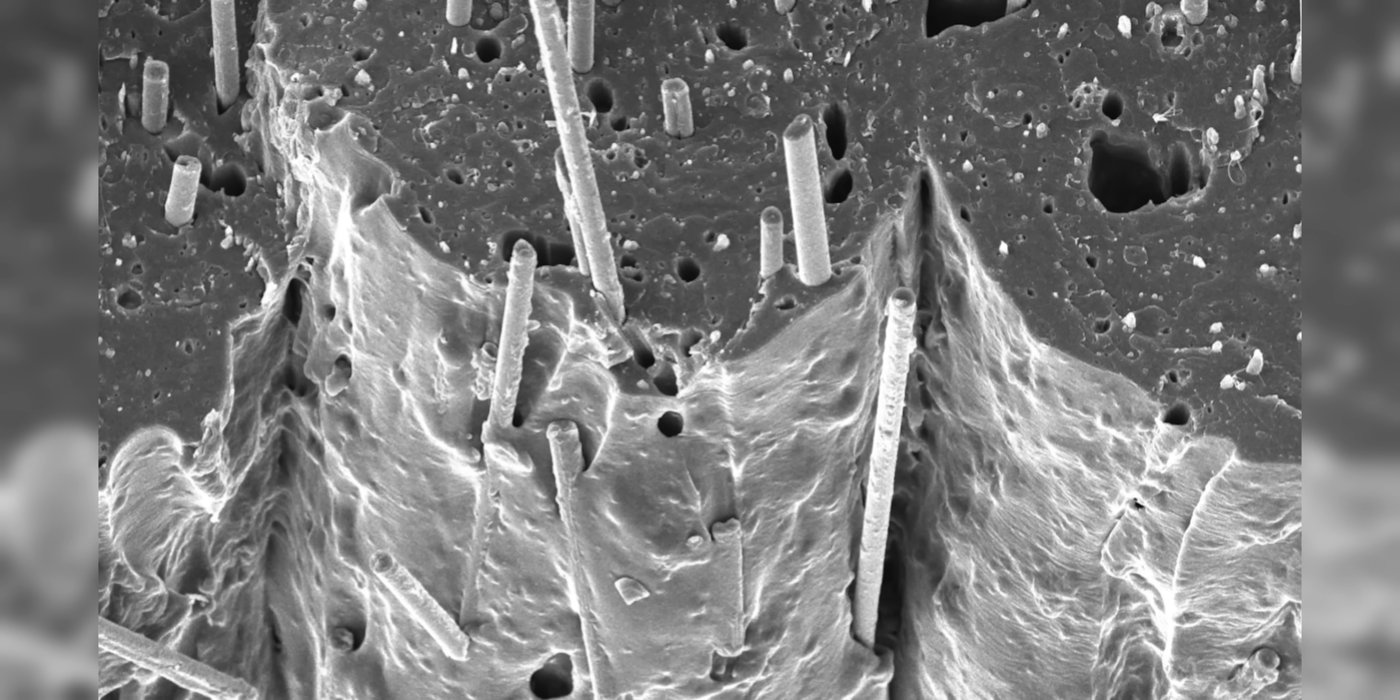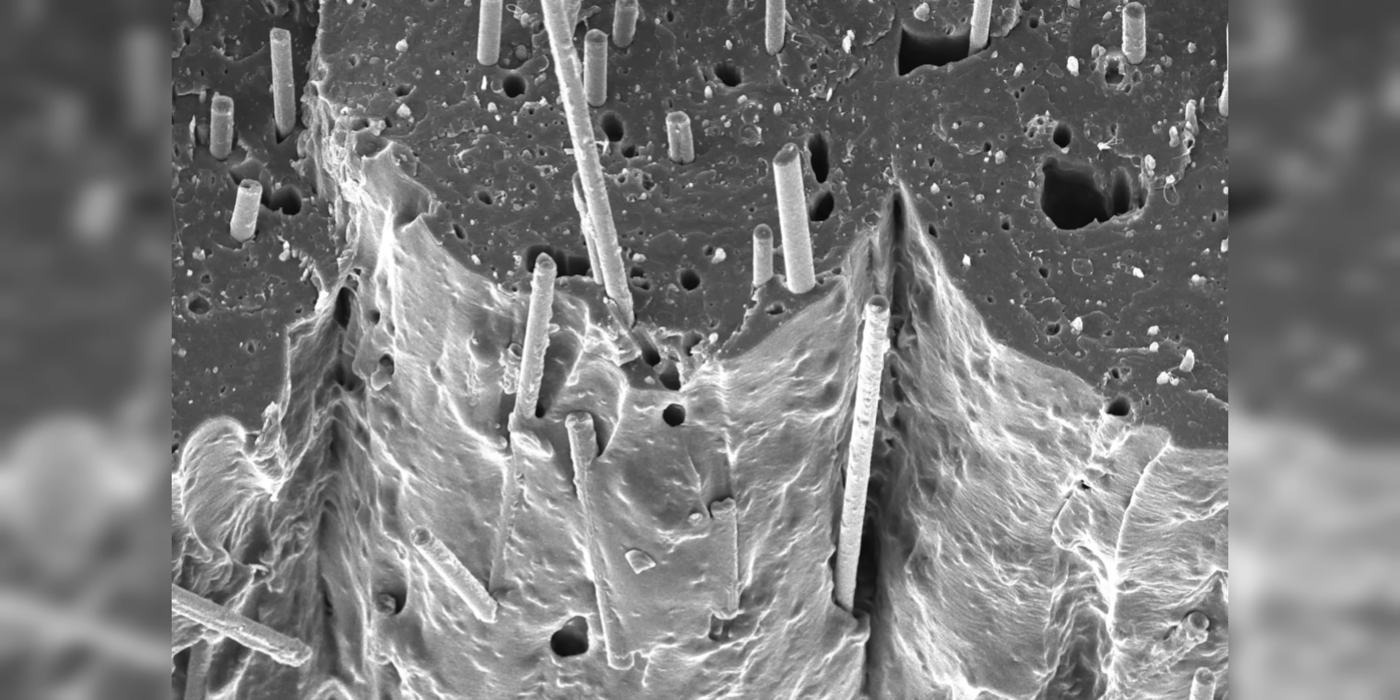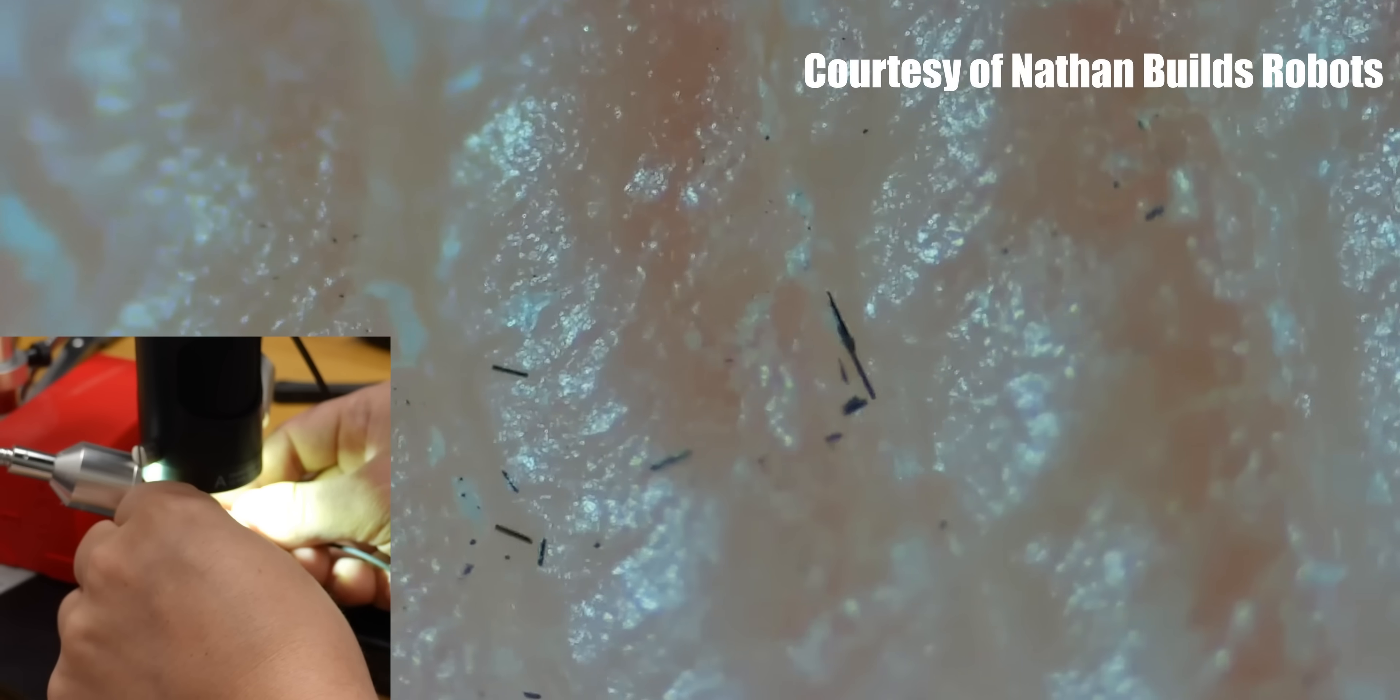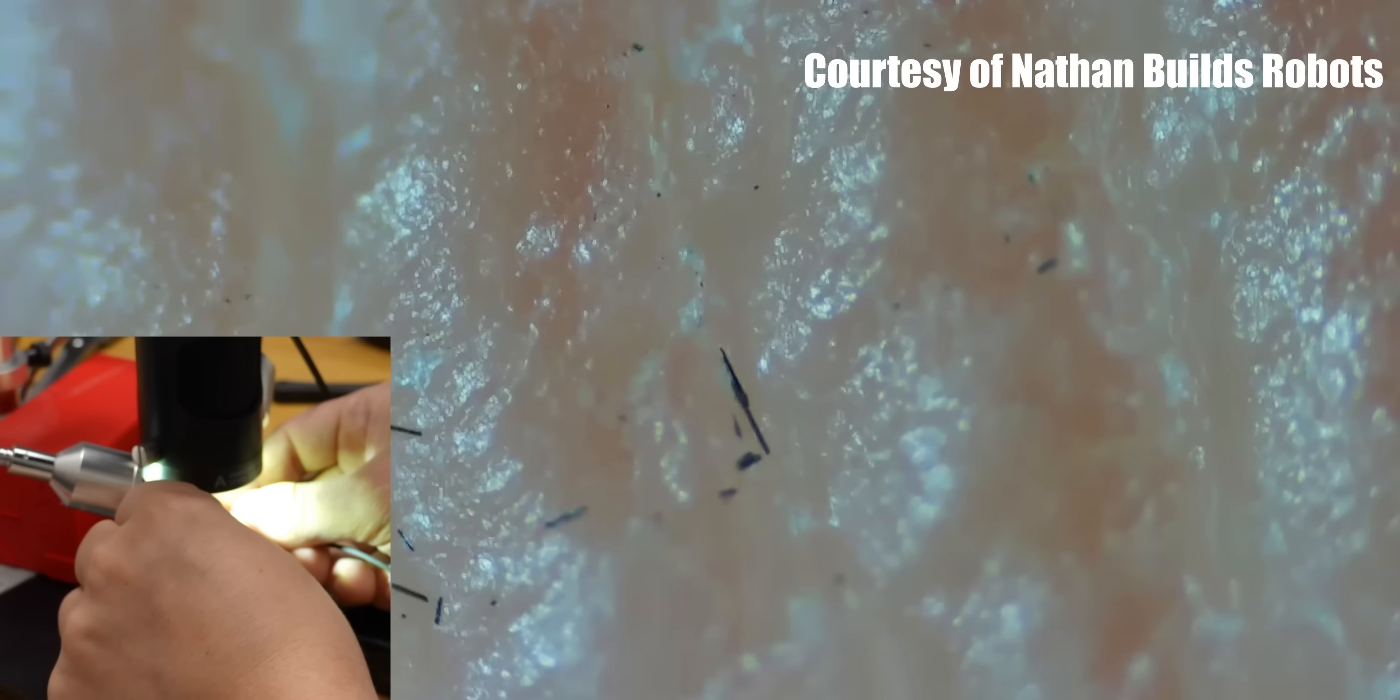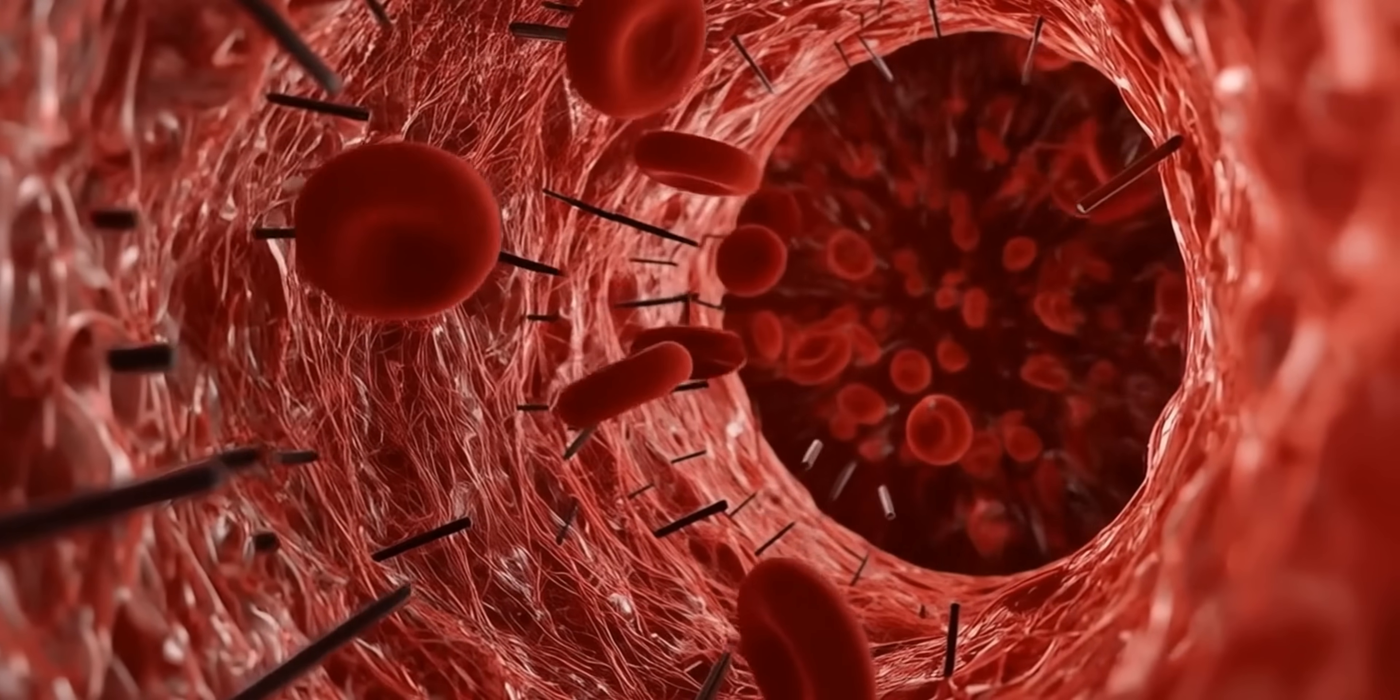What we haven't touched so far is there are other problems with PLA CF. If you handle those parts, the fibers that I showed you that are on the outside of the extrusion actually will break off and embed themselves into your skin. You could also brush them into the air and breathe them in. So in my profession, in medical 3D printing, everything containing carbon fiber that isn't completely encapsulated in, for example, resin or whatever, is actually out of the question for manufacturing. Because the MDR, the Medical Device Regulation, says that carbon fiber is a risk factor. Because carbon fiber shards, when they break, they get so tiny and so needle-like that they basically can pierce the walls of your cells and damage them. That might be another investigative video, if you like, if we want to look into the health risks of carbon fiber.